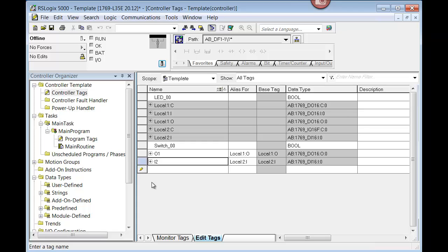So these are variables that we are declaring, but in an SLC500 they would have been pre-declared. Now I/O will always have module defined tags, but they're not pre-declared by you. When you add the module to your I/O tree, it puts these tags right in. So these are pre-declared variables specific to the I/O modules.